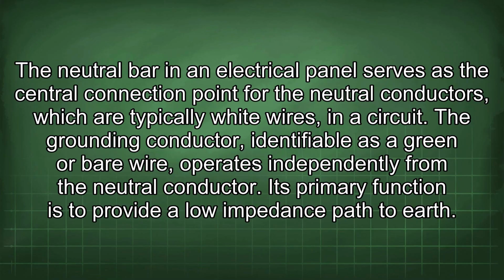The neutral bar in an electrical panel serves as the central connection point for the neutral conductors, which are typically white wires, in a circuit. The grounding conductor, identifiable as a green or bare wire, operates independently from the neutral conductor. Its primary function is to provide a low impedance path to earth.